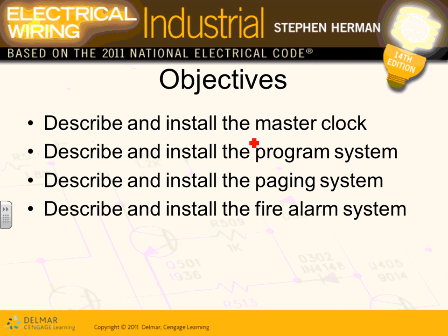For time, we have the master clock system that you guys installed — 15-inch and 12-inch clocks in different locations on the manufacturing floor. We also have a program system to communicate breaks via signals. We have a paging system where you can page certain people — we installed not less than two speakers in every room, placed 20 to 25 feet on center. And then there's the fire alarm system.